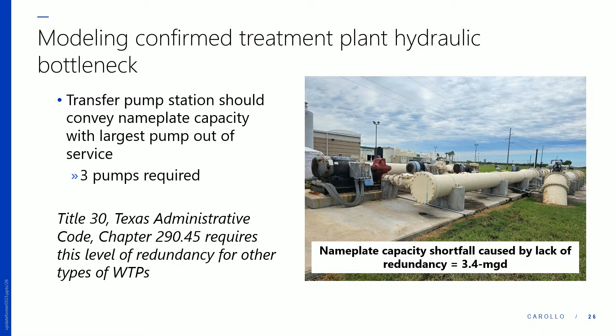If one pump were to go down, the impact on the nameplate capacity is 3.4 million gallons per day. So one of the recommendations is—this was intended to be built out with a fourth pump—let's add the fourth pump for that reliability purpose that was intended in the code, though not required for this type of treatment plant.